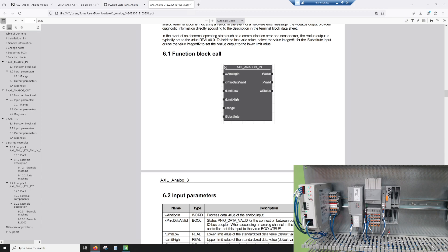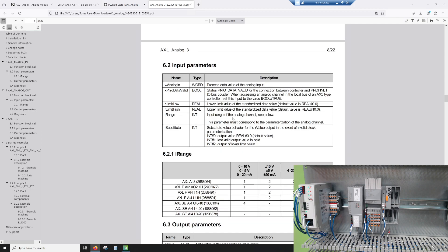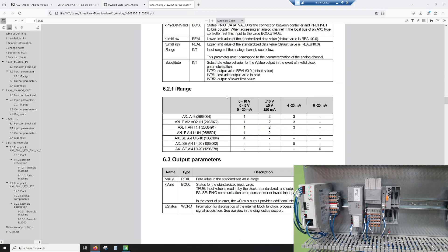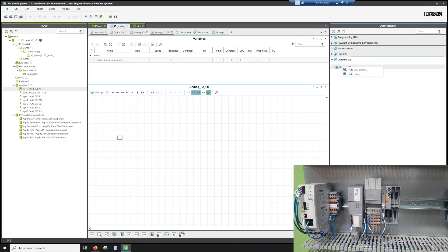The block also has low limit, high limit, range, and substitution parameters. In the range you match up the card you have — for an AXL AI8 doing zero to 10 volt input you put a 1, and for 4 to 20 milliamp you put a 3. If you were using the smart elements card it gets a 5, mainly because that changes the scaling from zero to 30,000 counts to zero to 10,000 counts.